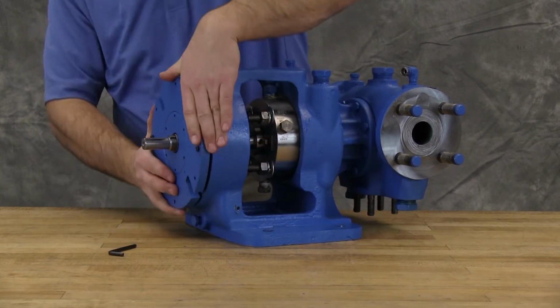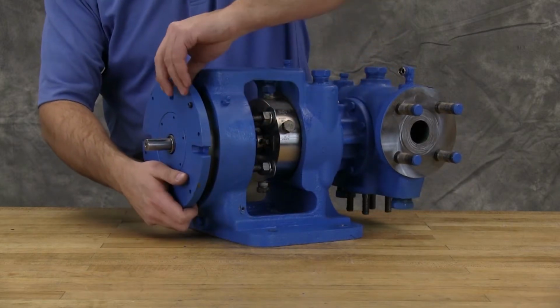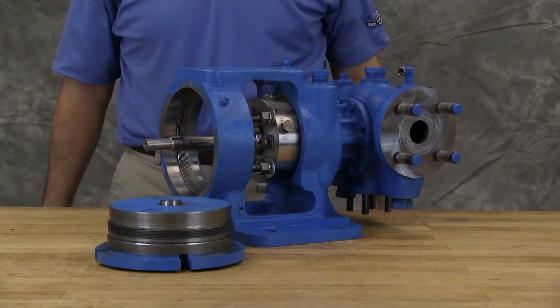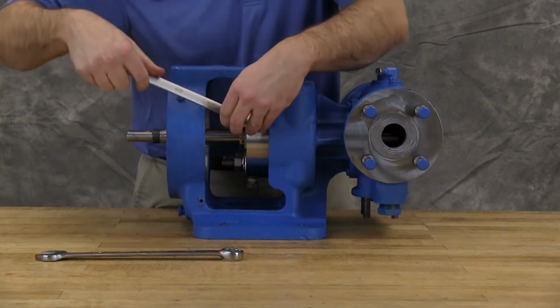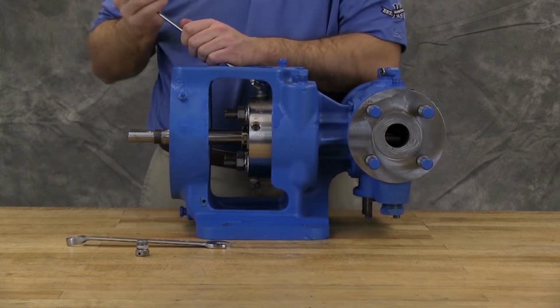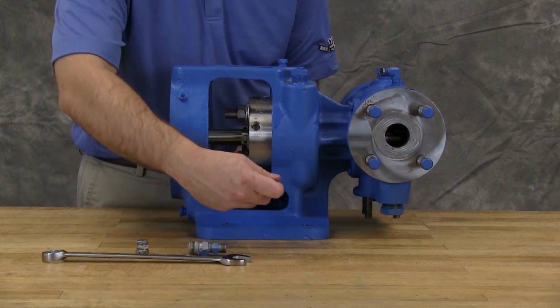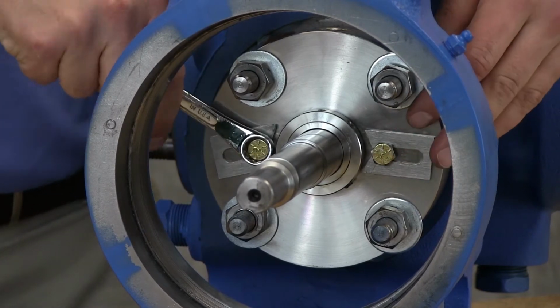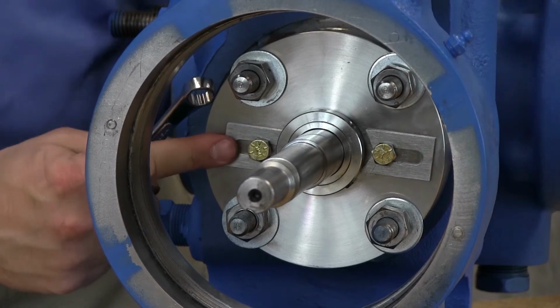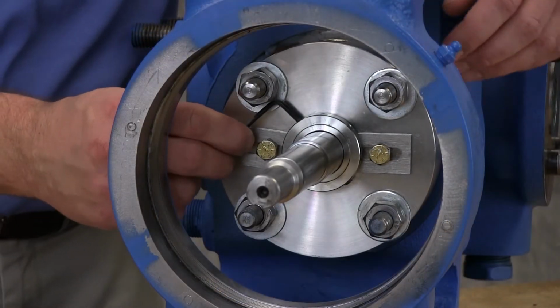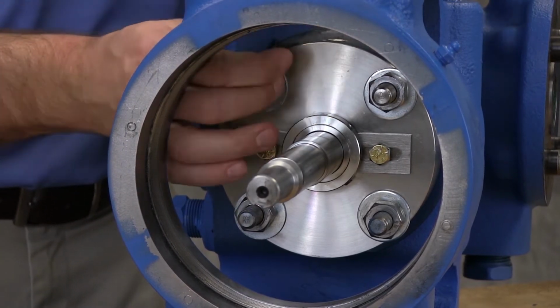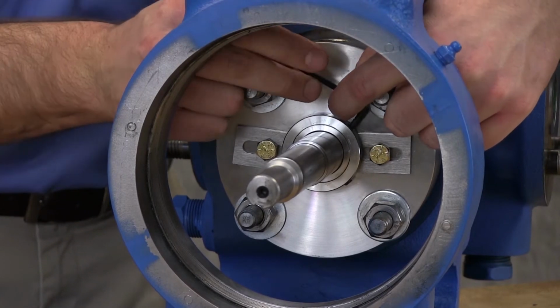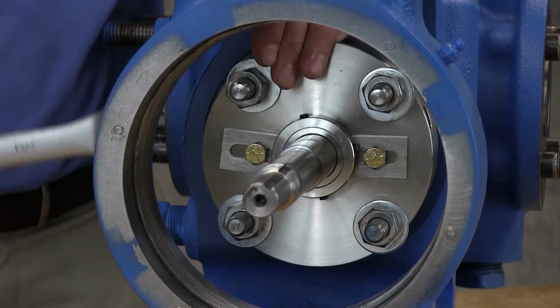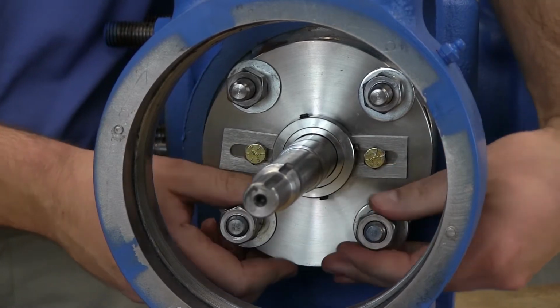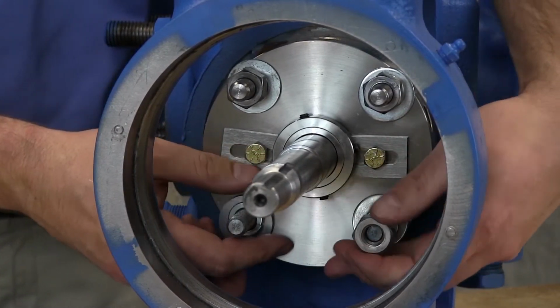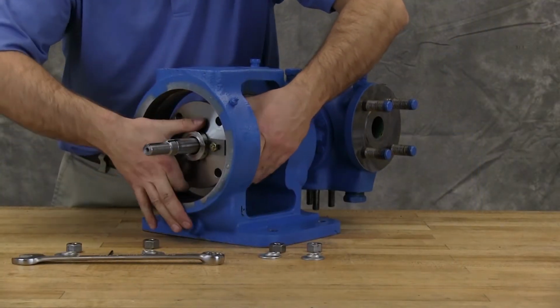Remove the pair of half-round rings under the inner spacer collar from the shaft for K through LS size pumps. There are no half-round rings on all other size pumps. Remove seal plugs or connections from seal gland. Place spacer clips on seal. Loosen the set screws on the cartridge seal collar to free the cartridge seal from the shaft. Remove nuts, lock washers, and washers from seal gland. Slide the cartridge seal out through the bearing housing opening.